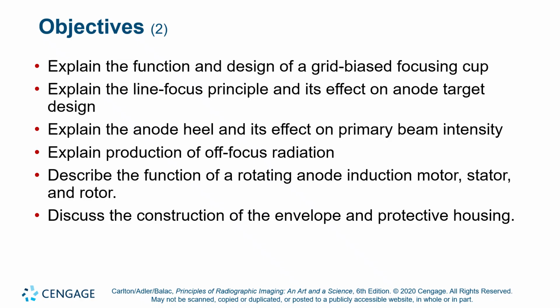Okay, not that hard. Now, why do we prefer a rotating anode? Is it an improvement to the design? Well, it takes a lot of work to convert to a rotating anode design, so there must be some justification for it. And the justification is you can stack a lot more heat on a rotating anode than you can on a stationary anode. So the heat capacity of the tube increases, and you can work the tube for longer exposures and bigger exposures before it overheats, or is at risk of overheating.